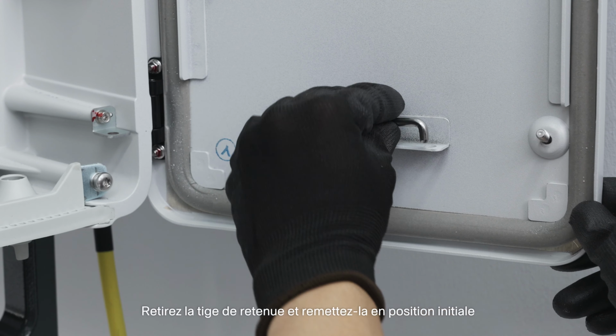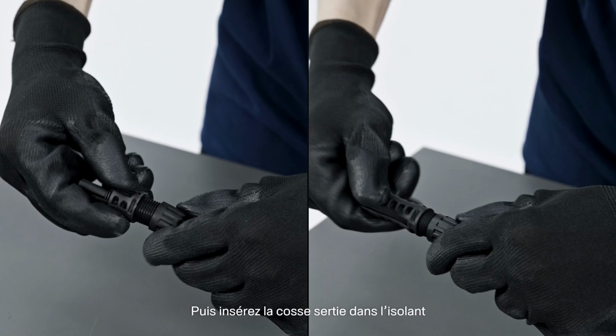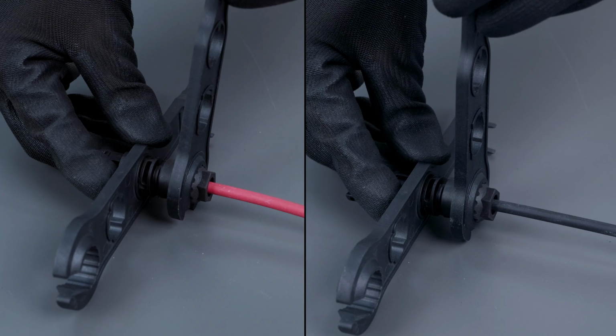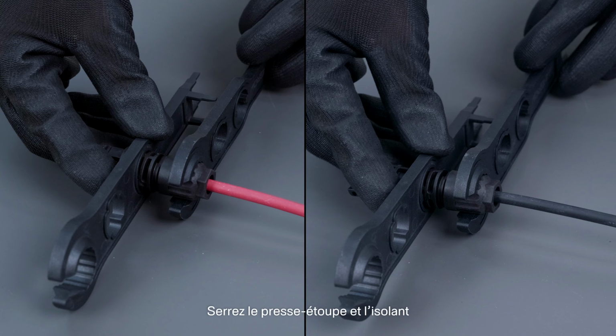4. DC cable connection. Strip the insulation from each DC cable by 8 to 10 mm. Assemble the cable ends with the crimping pliers. Lead the cable through cable gland and insert the crimp contact into the insulator. Tighten the cable gland and the insulator.